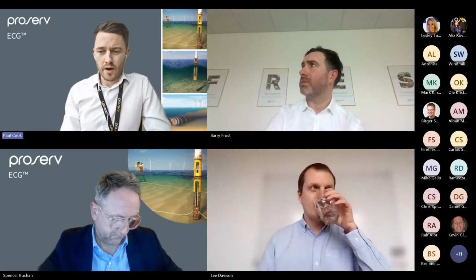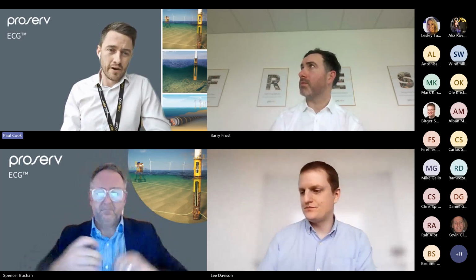I don't know if Paul or Barry want to add anything. Yeah, I think there are also industry statistics that haven't changed much over the last 5 years or so, where 70 to 80% of insurance claims are attributed to cable failures. If you dissect some of the failure modes within that, they're particularly around the termination area - I think the statistic is that two-thirds of cable failures are not the cable itself, it's actually the terminations, essentially where there is human intervention. Traditional monitoring systems like DTS and DAS do not have the ability to monitor terminations.